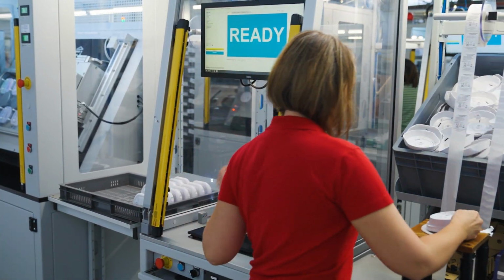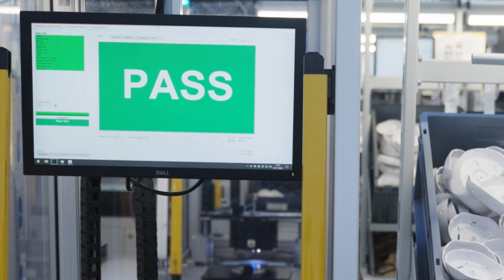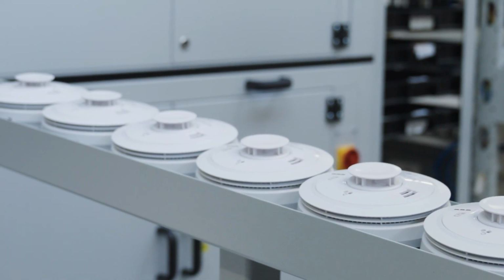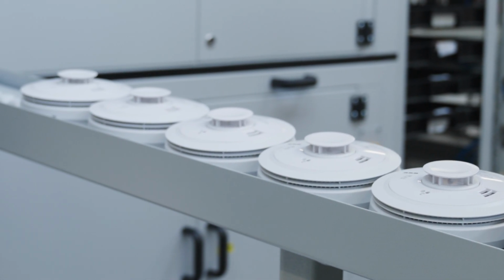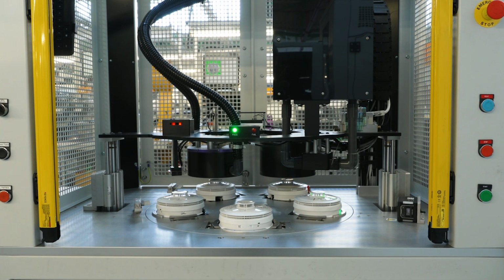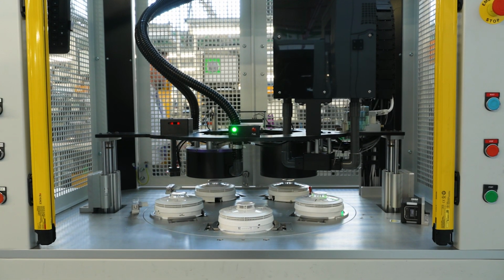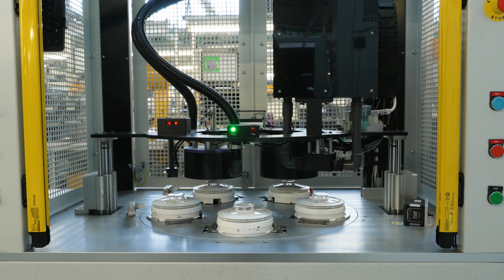It has to follow a flow and it's highly controlled. When a 3030 passes the CO calibration, it moves into our new multi-test stations. These test stations allow us to perform several tests in parallel, with up to 4 devices at the same time. We can do a smoke calibration step for the smoke sensor.